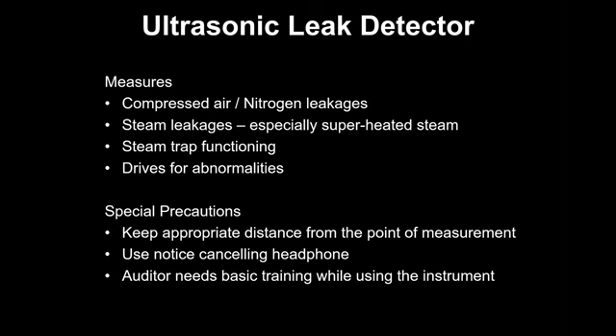Now, the main precaution is that you should use the noise cancelling headphone, because they provide a probe, and they keep saying that it can measure even up to 3 meters. Some probes say 6 meters, but that is more of an eyewash. So always use a noise cancelling headphone, so you can also hear that sound along with the digital display, or the deflection that shows with the probe. Because we have to use a noise cancelling headphone, the operator needs some training. Just anybody cannot do it. It needs training, maybe about 2 to 3 hours on how to use the instrument.